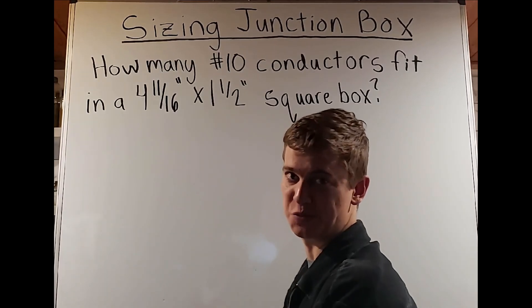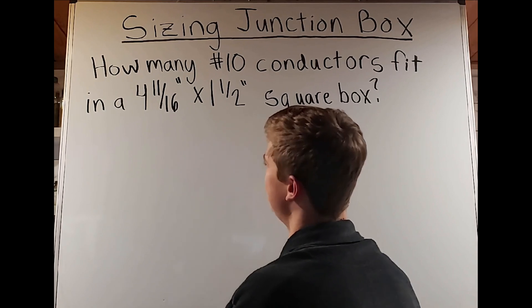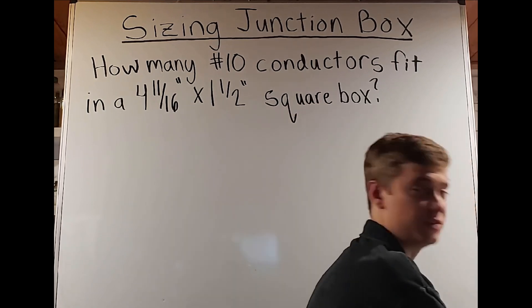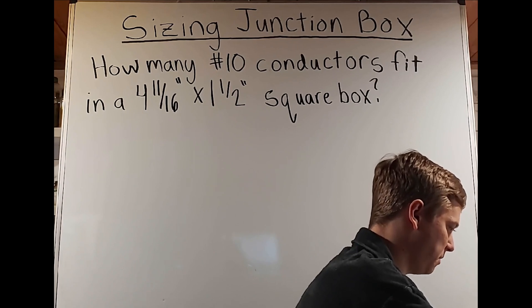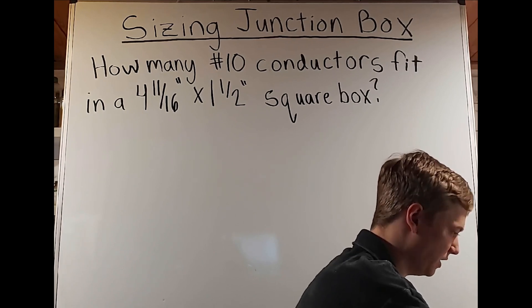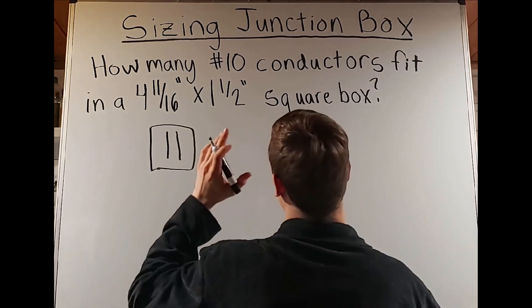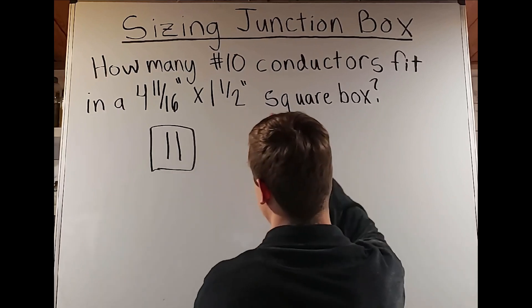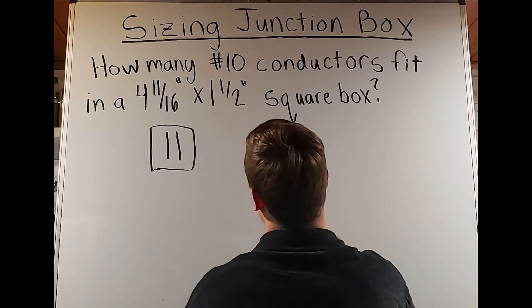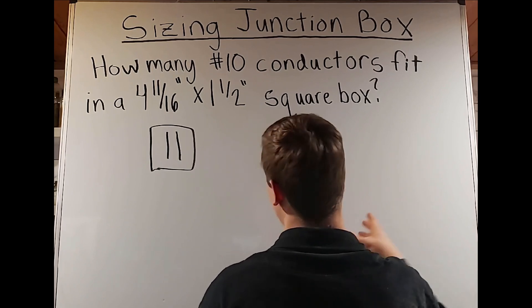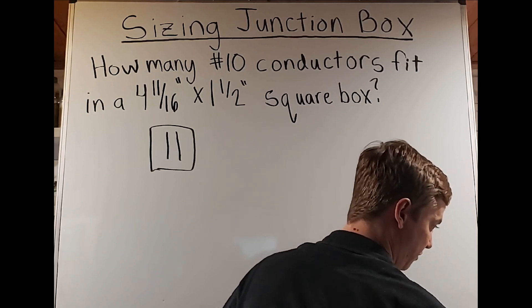These questions will get more complex. Next: how many number-10 conductors fit in a four-and-eleven-sixteenths by one-and-a-half inch square box? Using Table 314.16A, we find that size under square box and look under number-10 — we see the number 11. So 11 number-10 conductors fit in the four-and-eleven-sixteenths by one-and-a-half inch square box. The table already maps this out for us, similar to how Annex C simplifies conduit fill calculations.